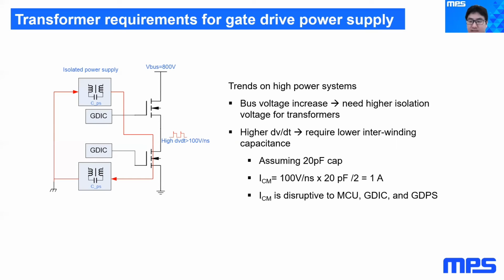Here we are showing an example. Assume each transformer has 20 picofarad capacitance between primary and secondary side, which is very typical for an off-the-shelf transformer, and the silicon carbide MOSFET switching slew rate is assumed to be 100 volt per nanosecond. Then the common mode current across the isolation boundary will be 1 amp, which can obviously be destructive.